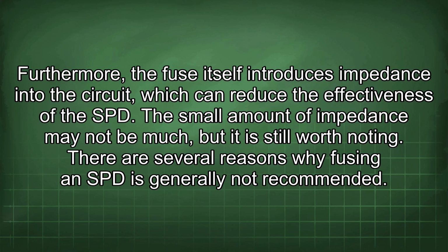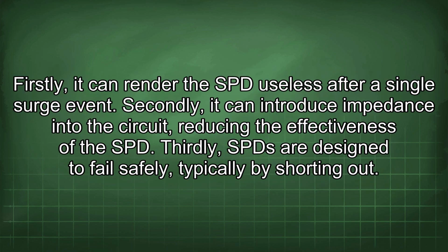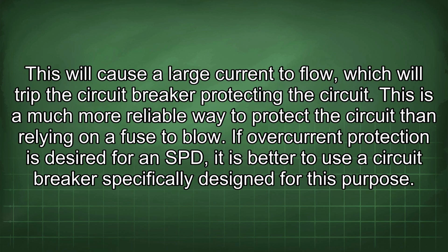There are several reasons why fusing an SPD is generally not recommended. Firstly, it can render the SPD useless after a single surge event. Secondly, it can introduce impedance into the circuit, reducing the effectiveness of the SPD. Thirdly, SPDs are designed to fail safely, typically by shorting out. This will cause a large current to flow, which will trip the circuit breaker protecting the circuit. This is a much more reliable way to protect the circuit than relying on a fuse to blow.